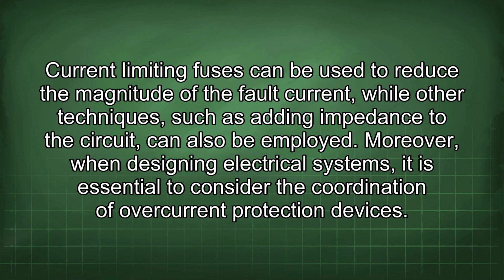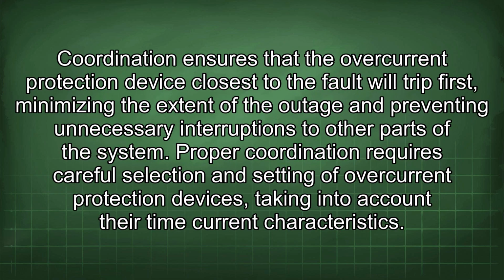Moreover, when designing electrical systems, it is essential to consider the coordination of overcurrent protection devices. Coordination ensures that the overcurrent protection device closest to the fault will trip first, minimizing the extent of the outage and preventing unnecessary interruptions to other parts of the system. Proper coordination requires careful selection and setting of overcurrent protection devices, taking into account their time current characteristics.